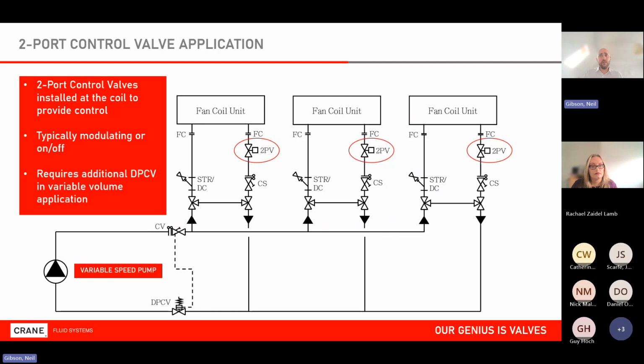Typical use of 2-port valves, as you'd expect, is on a terminal device, and we modulate those in response to demand. Now, typically speaking, in a variable volume system, we'd also have other components to help us. On the mechanical side, we'd use something like a commissioning set to help us balance the system. And then we'd have something like a differential pressure control valve, you can see there next to the pump.